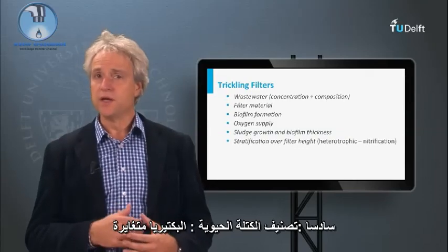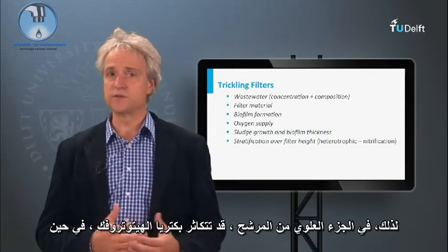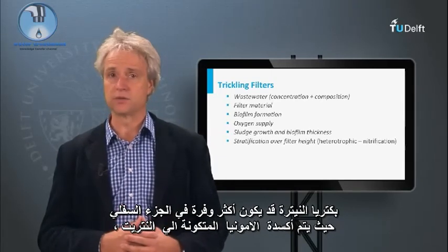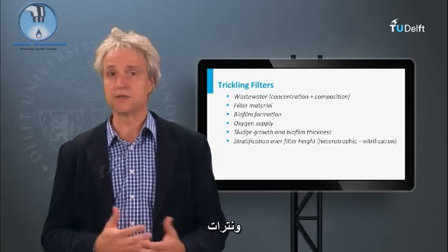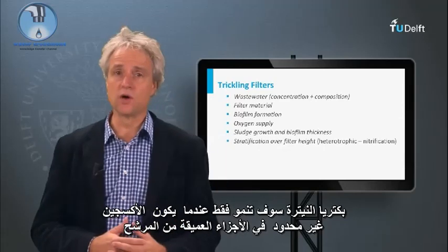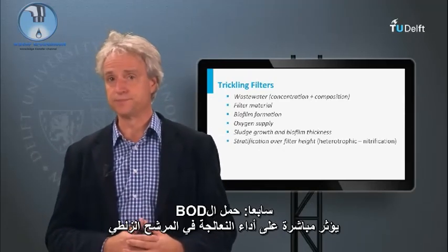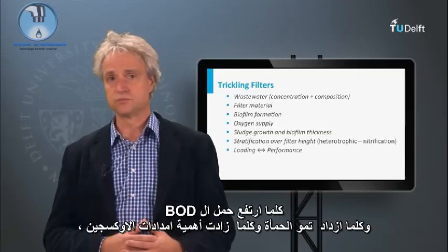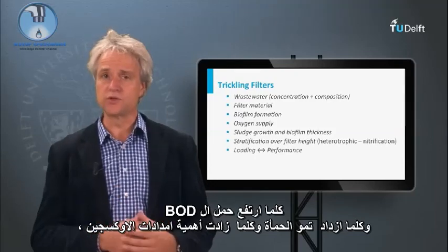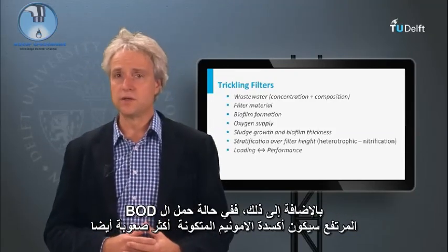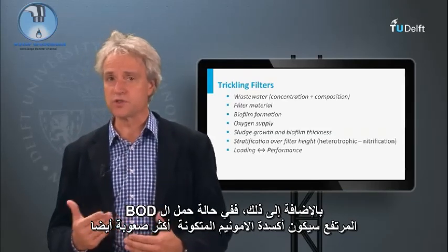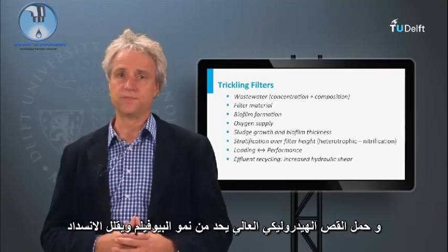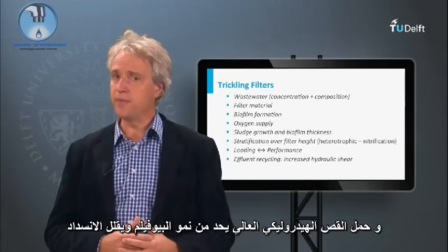Six, biomass stratification. Heterotrophic bacteria oxidizing carbon grow much faster than nitrifiers. Therefore, at the top part of the filter bed, heterotrophs may proliferate, whereas nitrifiers might be more abundant at the bottom part, where the formed ammonium is oxidized to nitrite and nitrate. Nitrifiers will only grow when oxygen is not limited in the deeper parts of the bed. Seven, the applied BOD loading will immediately impact the treatment performance. The higher the BOD load, the more sludge will grow and the more crucial the oxygen supply will be. At a high BOD load it will be more difficult to also oxidize the formed ammonium. Eight, biofilm growth can also be controlled by applying effluent recirculation. A higher hydraulic shear limits the biofilm growth and minimizes clogging.